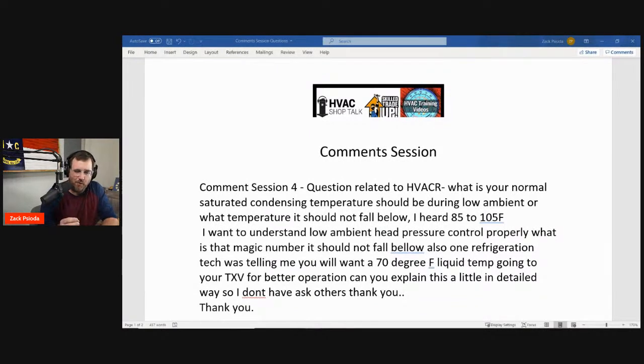So let's go where we cut off for TXV charging. TXV charging is usually cut off in the 70 degrees area. If it's cut off in the 70 degrees area for TXV charging, then that would give you a 90 degree, 20 degree over ambient. So 70 degree ambient, you're looking at 90 degrees right there. That's probably pretty close to being the number. That might be on the high end of the cutoff, because it says you can charge piston systems, which may or may not be what they're talking about, at 55 degrees outside. That would put it at 75 degrees saturation, which is really low to me. So I don't know about that.